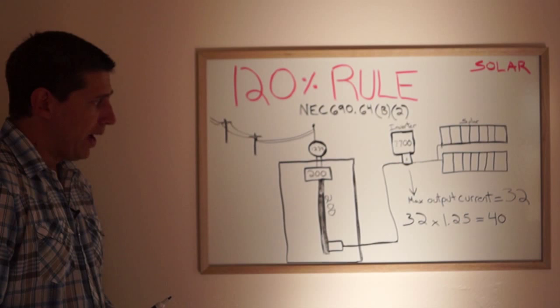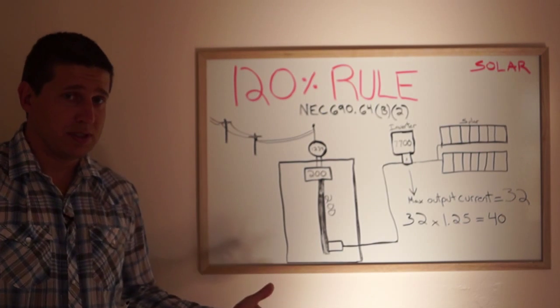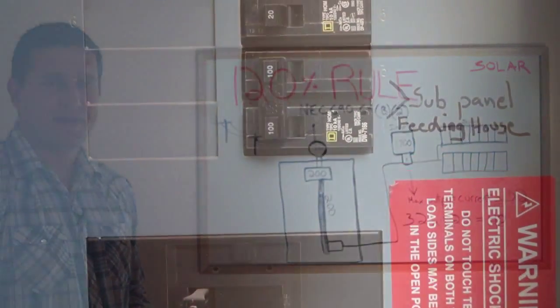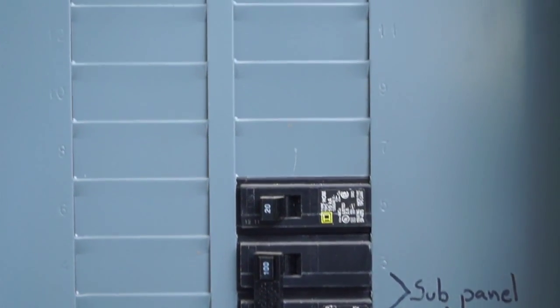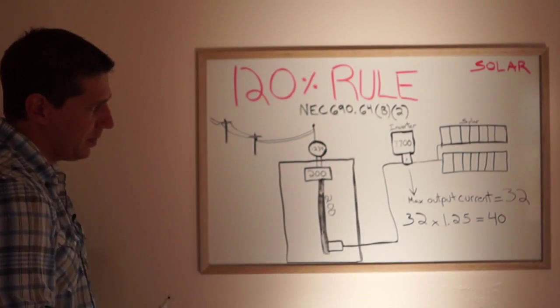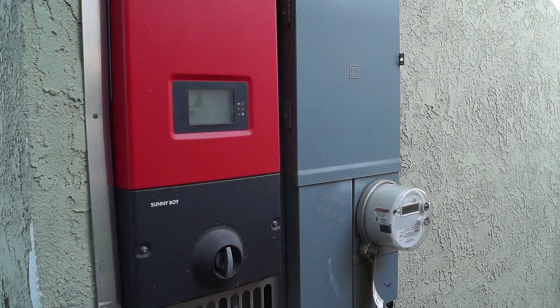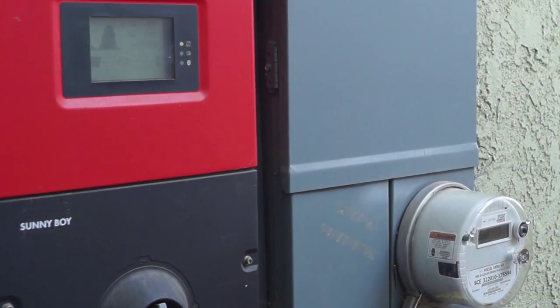Now when you have a solar system installed there's another code that states you have to install it on the opposite end of the bus bar from the main breaker. So here's your solar breaker. It's connected to the inverter and the solar panels. Inverter inverting it to 240 AC, solar coming in a DC high voltage.